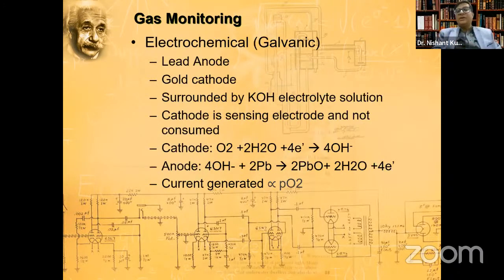Now, the most common one is the electrochemical or the galvanic, where we have the lead anode and the gold cathode, which is surrounded by potassium hydroxide electrolyte solution. Cathode is the sensing electrode and is not consumed, which is the gold.